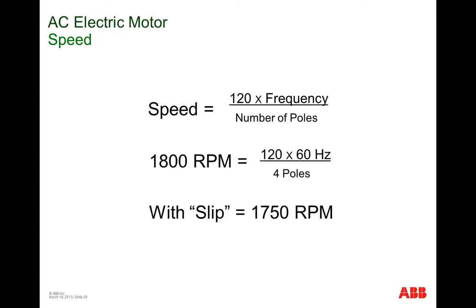Hey folks, I promise not too much math on this webinar, but I wanted to show this simple equation for the speed of a typical AC motor. Notice that frequency does not ever change. Incoming power is always at 60 hertz when it comes into the building. The number of poles does not change since they're built into the motor, and the 120 in the numerator is a constant. Therefore, the speed of the motor is always a constant 1,800 RPM.